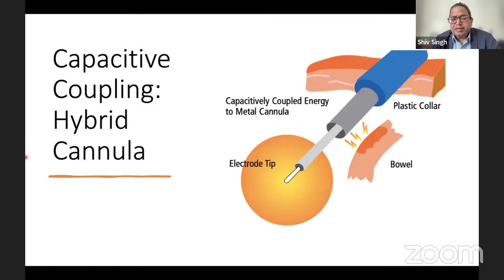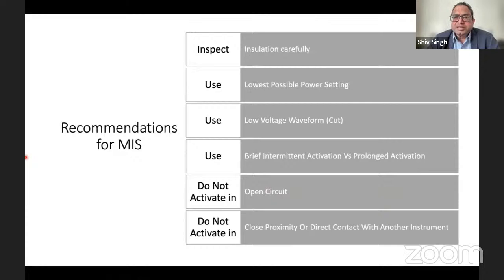Okay. So the recommendations are that we should inspect the insulation, use the lowest power possible for cutting and coagulation, use the lowest voltage waveform when cutting, and use brief intermittent activation instead of using it for long cutting procedures. And do not have open circuits, because the foot plates can sometimes be accidentally pressed, even though you're not using it. It can be pressed by other people. So make sure there are no open circuits available. And do not activate in close proximity or direct contact with another instrument. There should be no direct contact with another metal instrument when using diathermy. Keep it away from the diathermy itself.